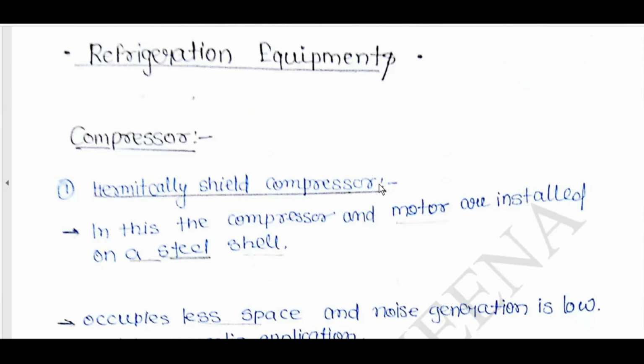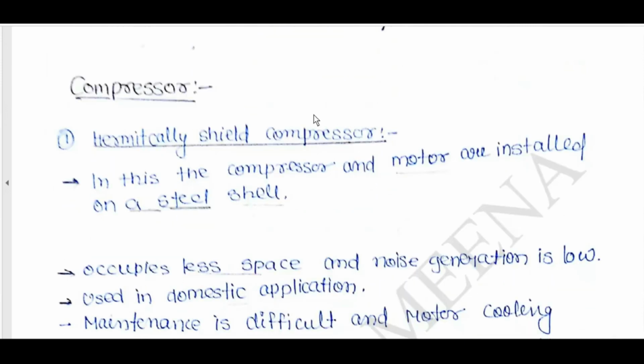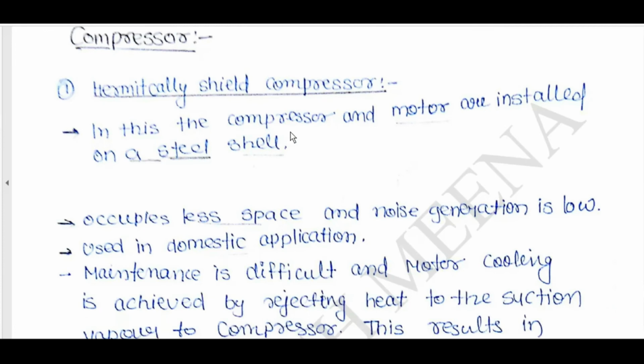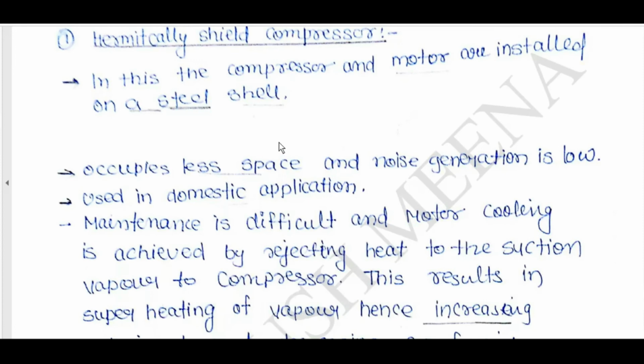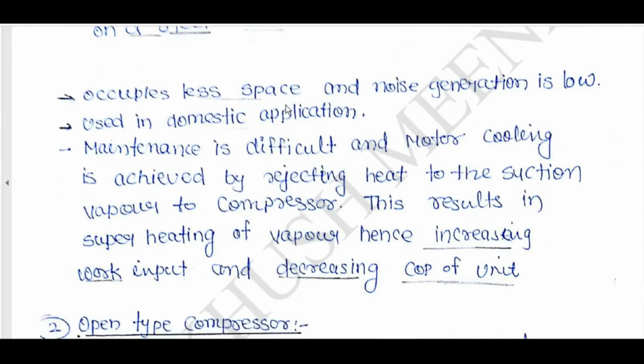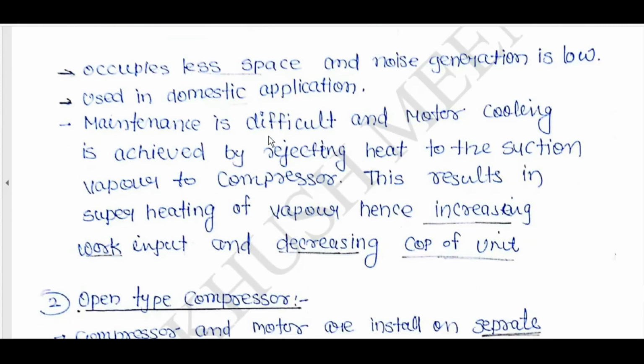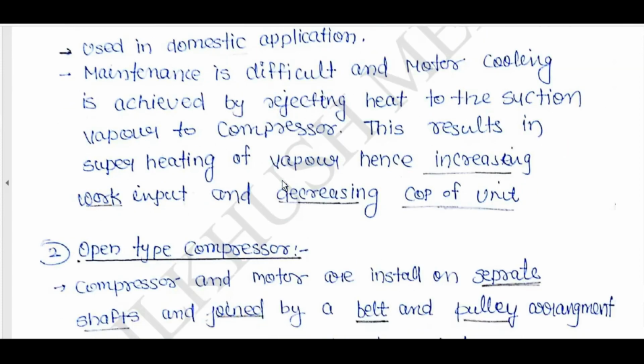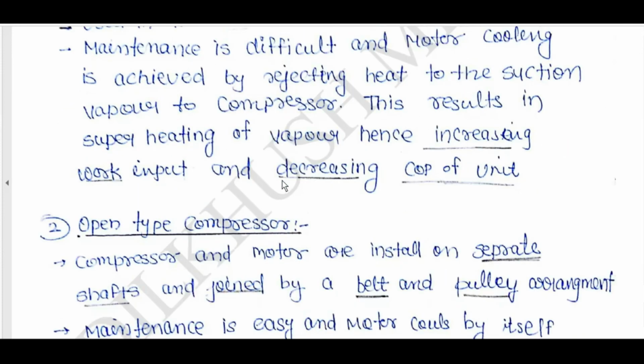Refrigeration equipment: compressors. Hermetically sealed compressor. In this compressor, the motor is installed in a steel shell. It occupies less space and noise generation is low. Used in domestic applications. Maintenance is difficult and motor cooling is achieved by rejecting heat to the suction vapor at the compressor. This results in superheating of vapor, hence increasing work input and decreasing COP of the unit.